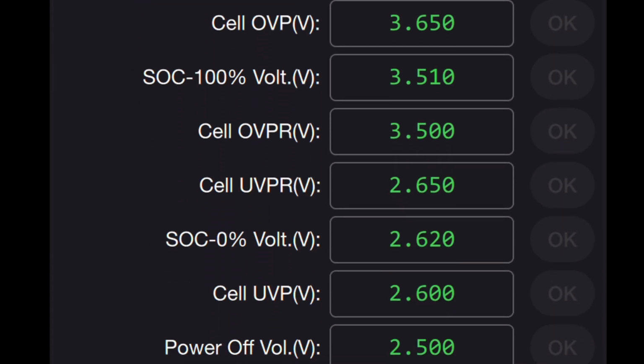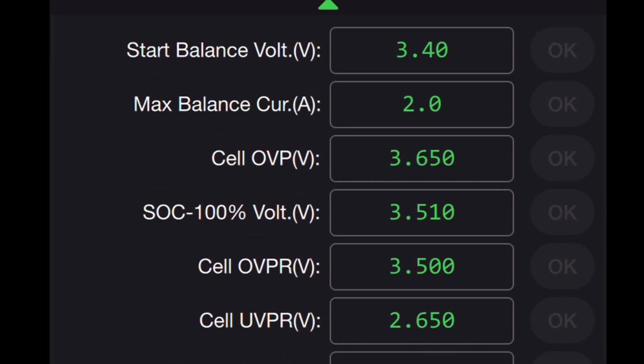You start off with the starting balance voltage. In other words, the cells have to reach 3.4 volts in order for the auto balancer to kick in. In addition to the configuration we did before, they have to be out of balance a certain amount before it happens. Then you have the max balance current, meaning it will transfer at most 2 amps from one cell to another at a time.